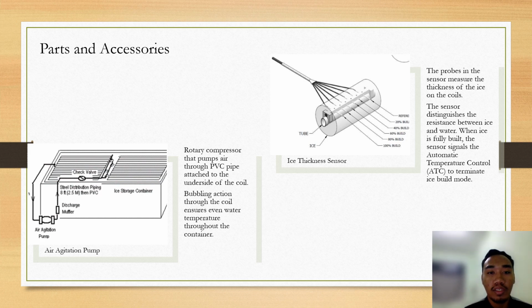The next accessory is the ice thickness sensor. The probes in the sensor are used to measure the thickness of the ice on the coil. The sensor distinguishes the resistance between ice and water. When ice is fully built, the sensor signals the automatic temperature control to terminate ice build mode. This means when ice is fully built in the ice storage tank, there will be signals sent to automatic temperature control to stop the process of ice building.